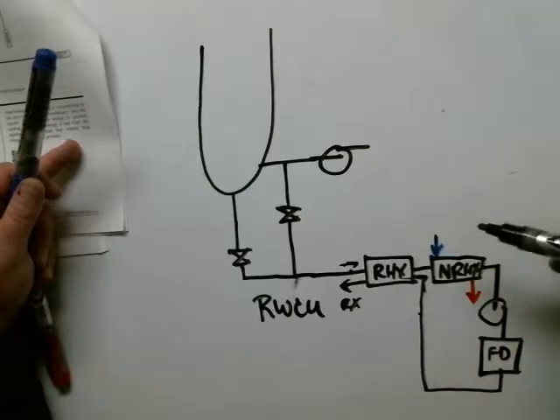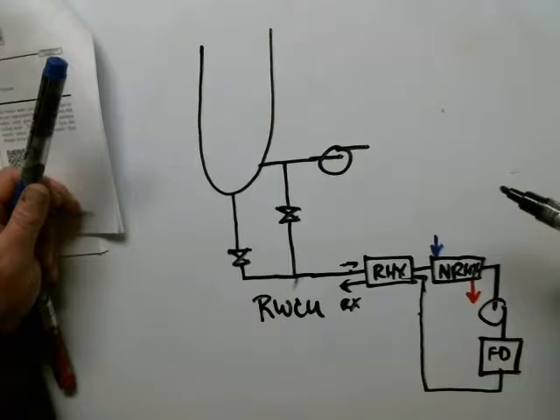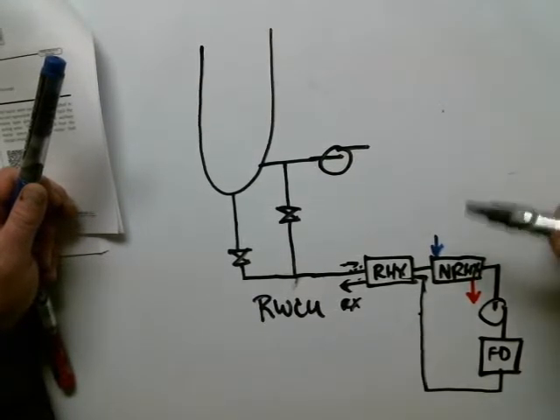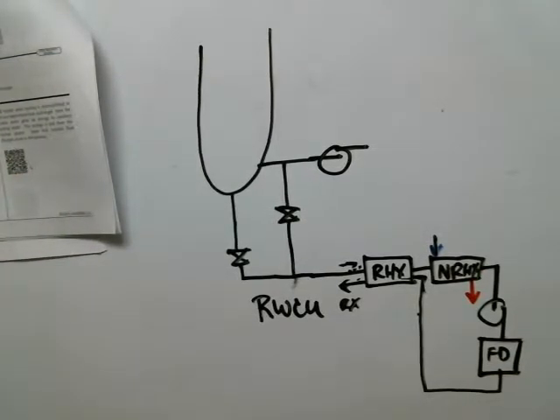So that's the uniqueness of a regenerative heat exchanger in that it doesn't have any external heating source. It uses the same fluid on both sides of the heat exchanger. It's just it's gone through a non-regenerative heat exchanger afterwards.